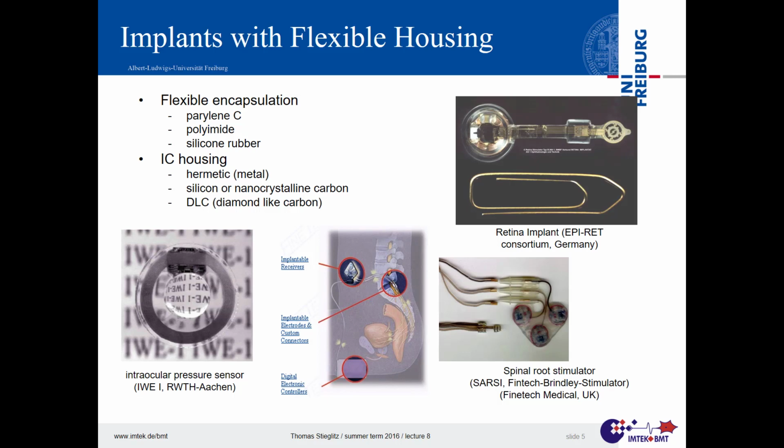used materials, mainly polymers. Might it be parylene C, might it be silicone rubber around. And in some cases, if you talk to persons who are implanting that, they are not very well aware why those things survive. They have their own imagination, and this is sometimes a bit different from what's really happening.